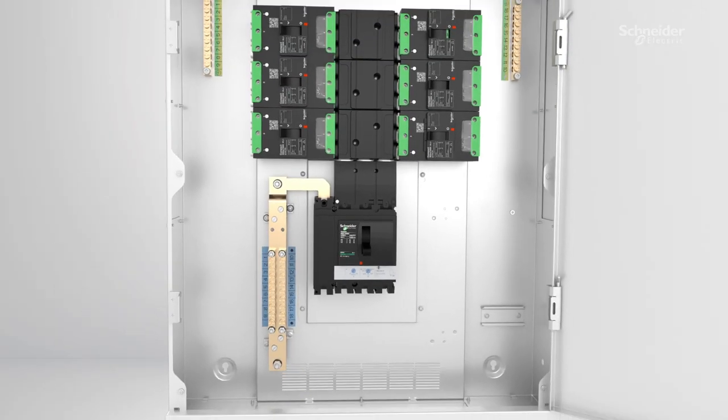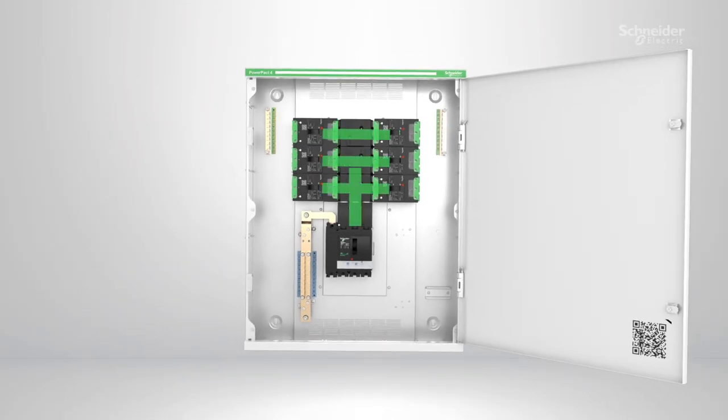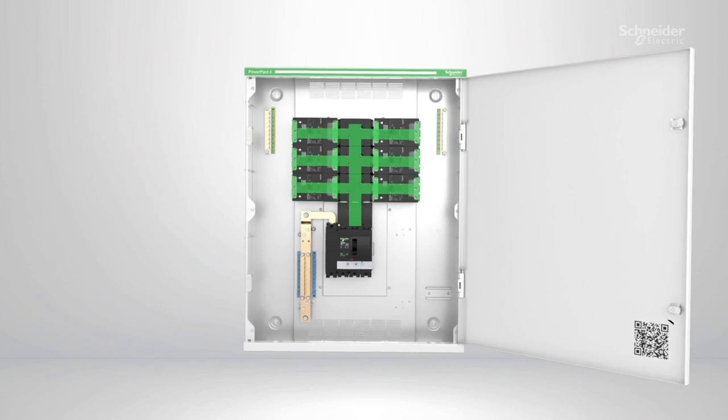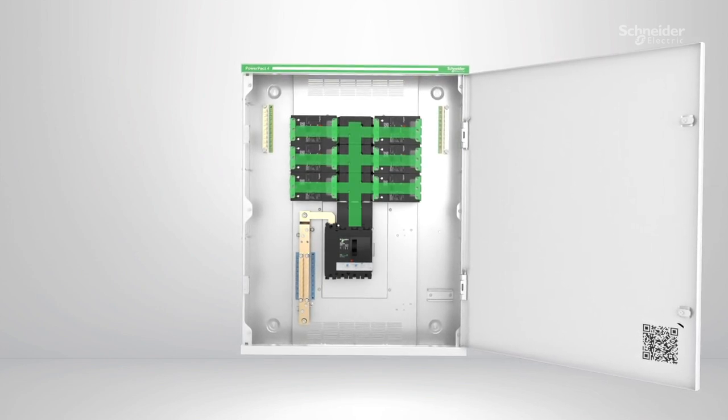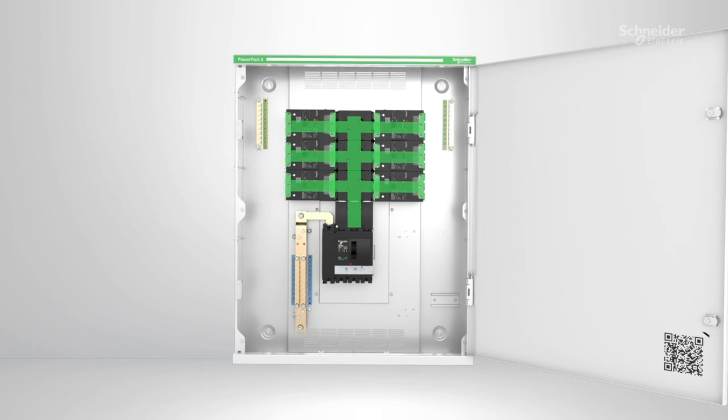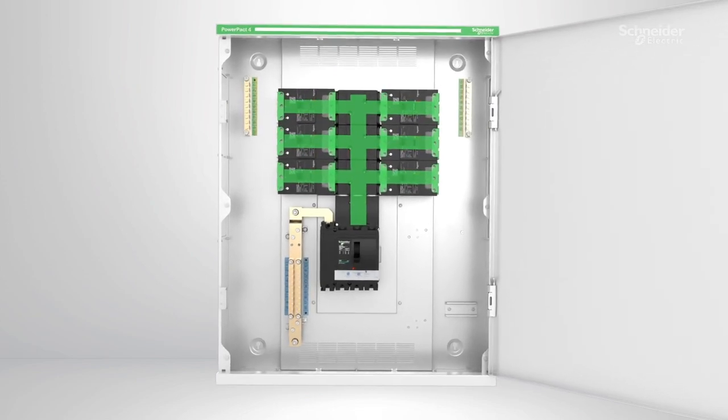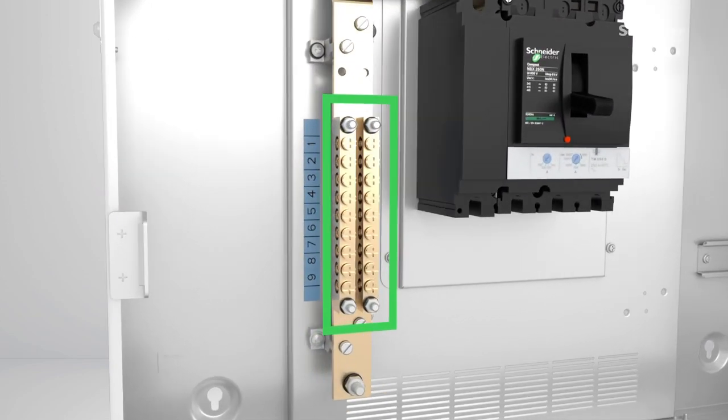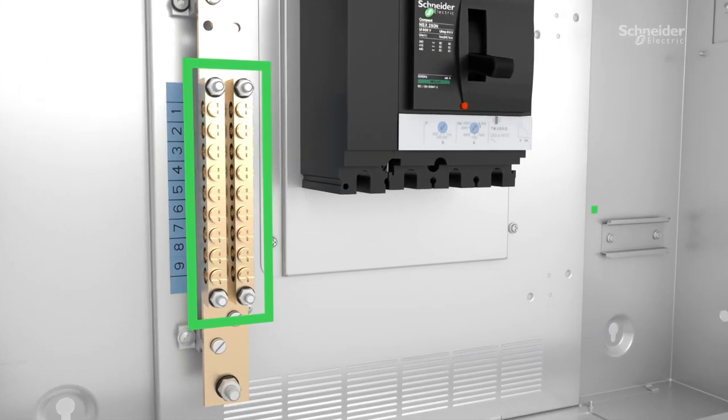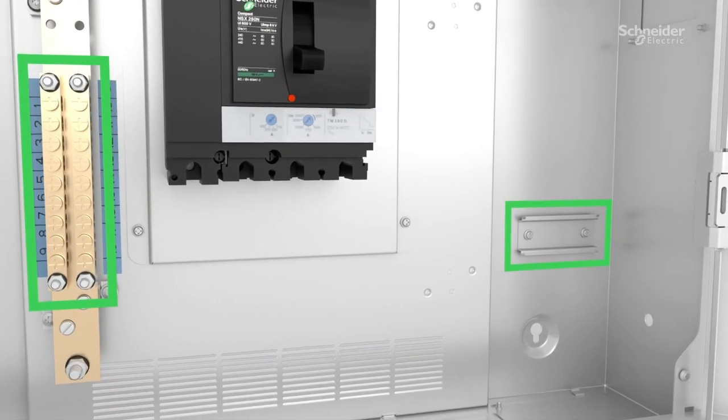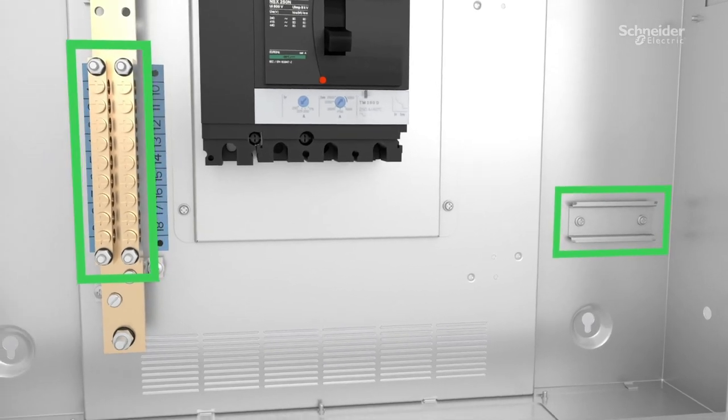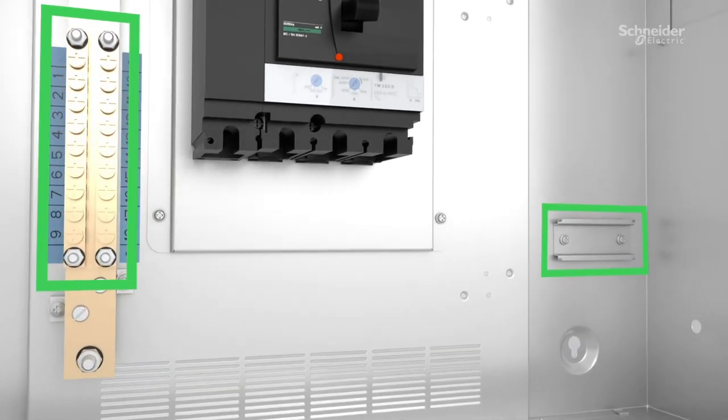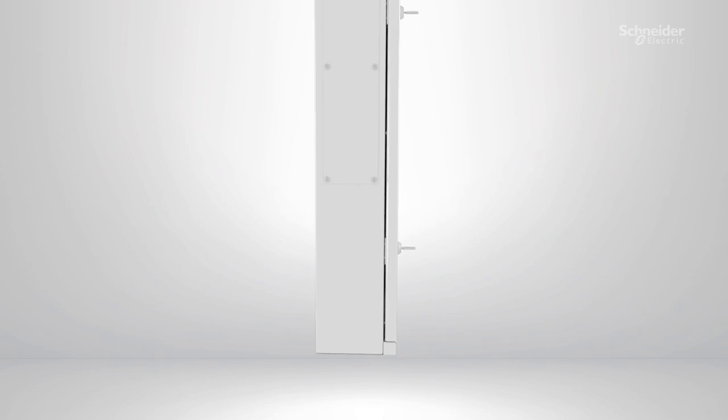The Fishbone busbar layout allows the NSX-M outgoing devices to be easily added while retaining the familiarity of the DIN rail position. Neutral bars are located toward the base of the unit for convenience, near the mounting point for DIN devices such as IFE and Concentrator, enabling monitoring of the board through our EcoStruxure applications.